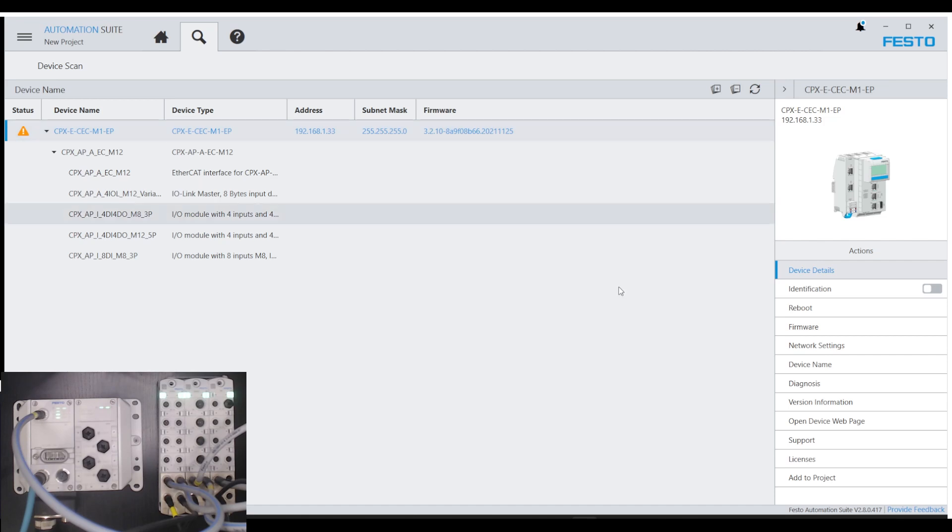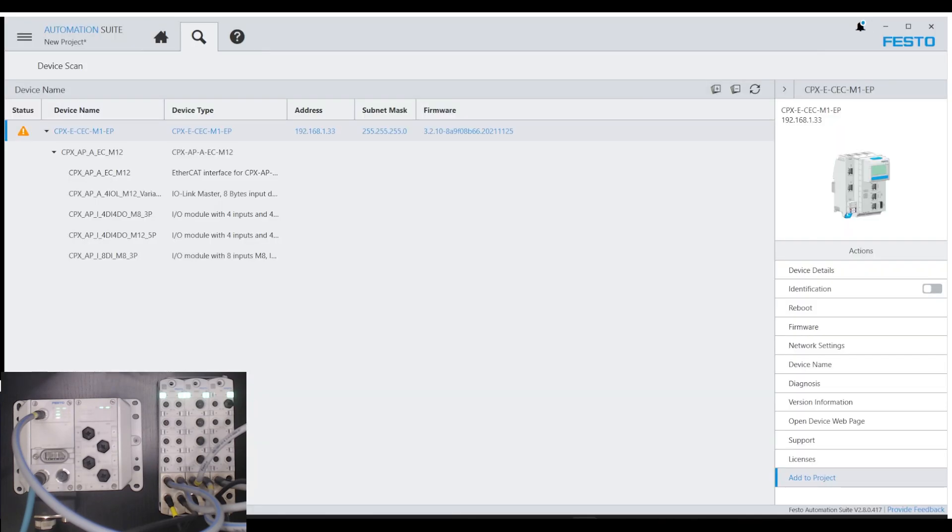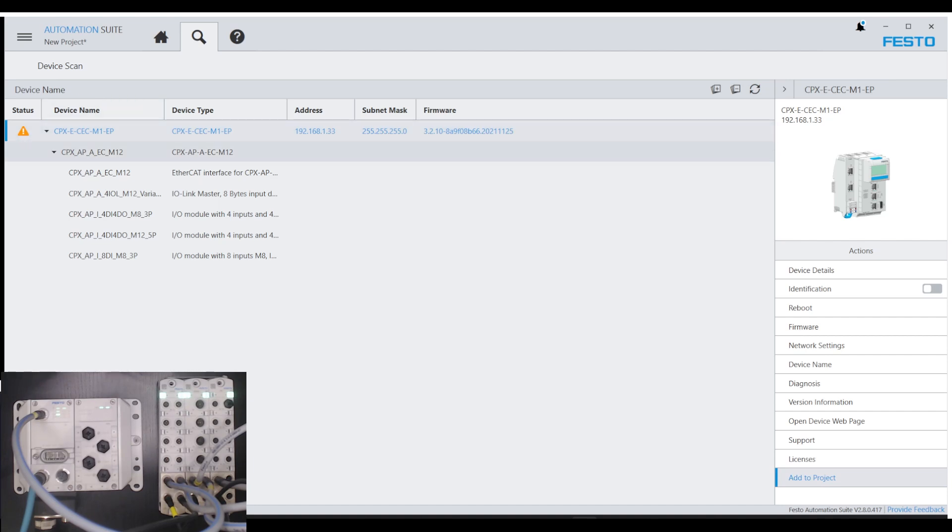If I have that PLC highlighted, I can click Add to Project. You'll be prompted several times to import the topology. So instead of just bringing in this first PLC at the very top, it will detect the IP20 slice rack that we saw earlier, as well as the APA and API modules. And so you get prompted a few times. I was prompted three times here to import all of those devices.